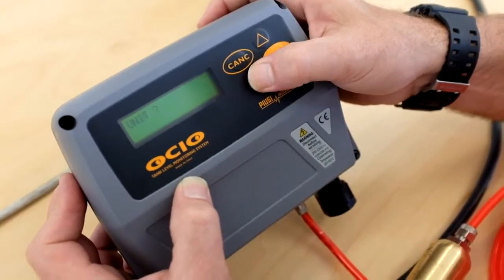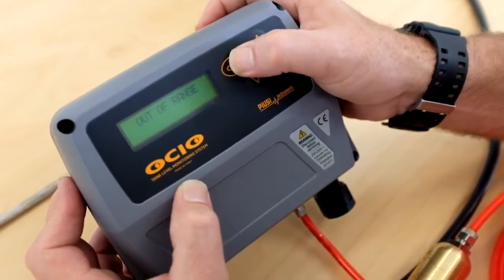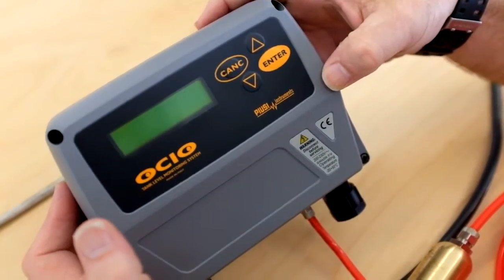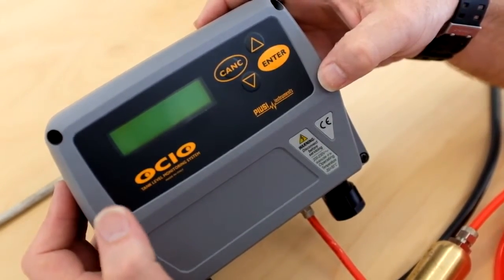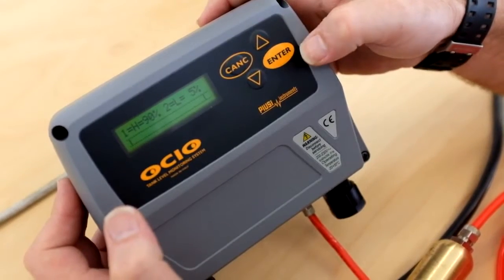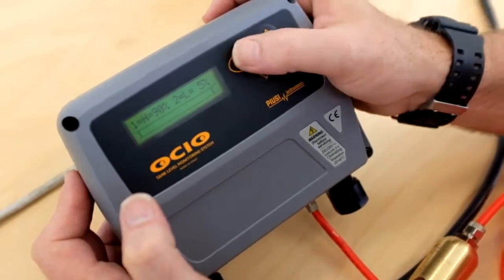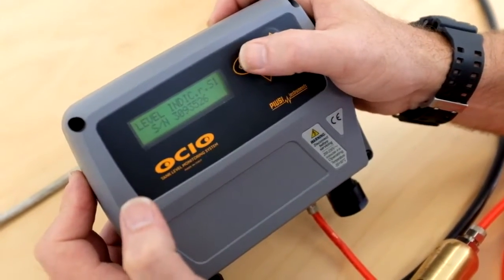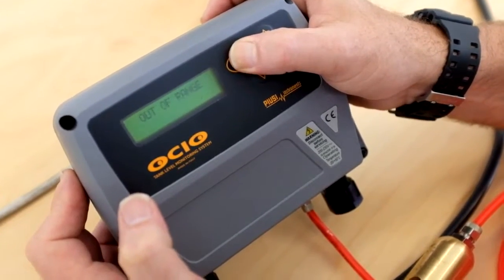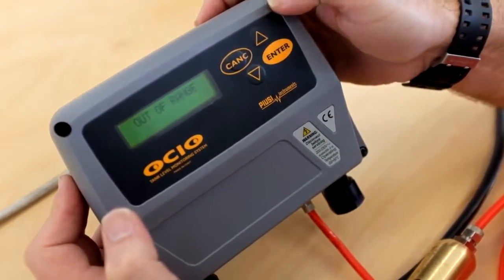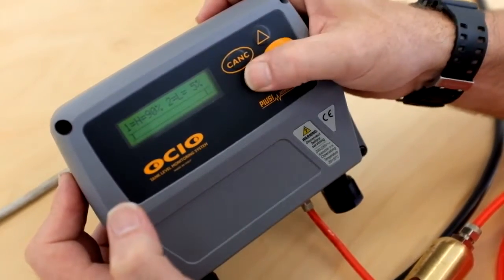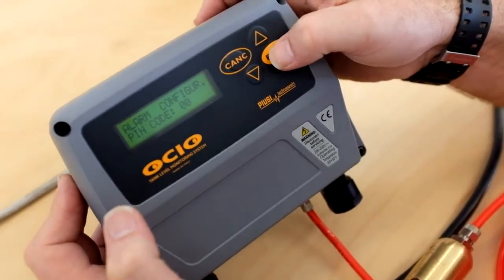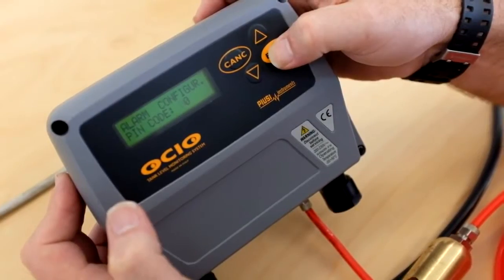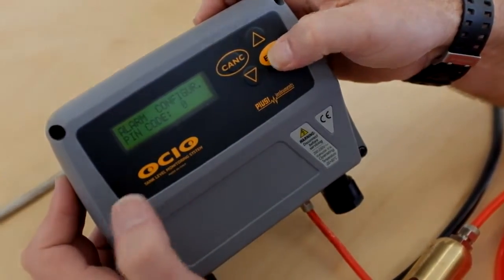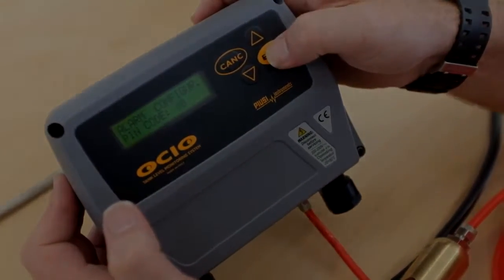So these up and down arrows, cancel takes you back. So now we're back out into general operation mode. Alright, I can press enter and it will show me the alarms, cancel back. If I hit cancel again, it goes back. So enter, I can see the alarms, I can go through configuration, the alarm. So I need the code 26 to configure the alarm via here. All right. So there we go.